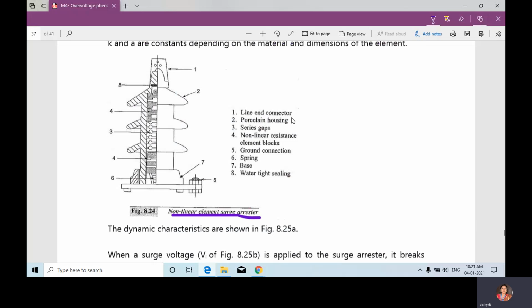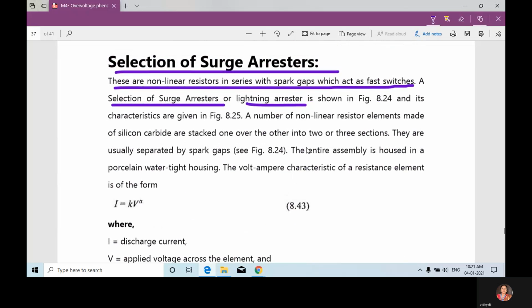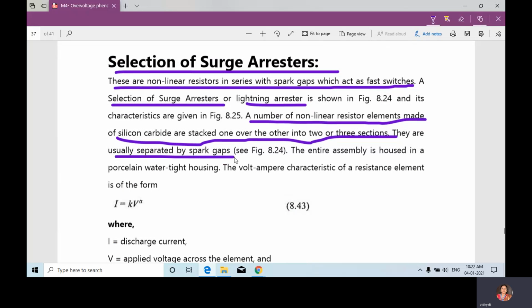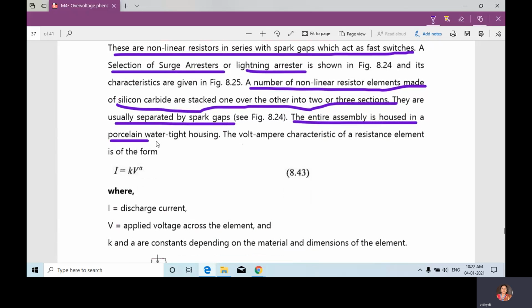One is a line end connector, 2 is a porcelain housing, 3 is a series gap, 4 is the nonlinear resistor element blocks, 5 is a ground connection, 6 is a spring, 7 is a base, and 8 is a watertight sealing. A number of nonlinear resistor elements made of silicon carbide are stacked one over the other into 2 or 3 sections. They are usually separated by spark gaps. The entire assembly is housed in a porcelain watertight housing.